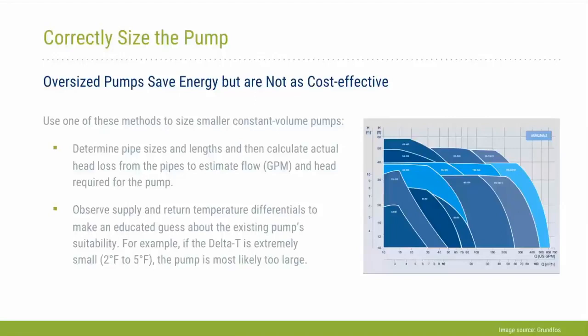I would say for a lot of these, you're probably going to see that the existing pump is oversized, and I would work with the manufacturer to help you right size that pump. As you can see for the domestic hot water ones, even though we had good energy savings, we got better savings and better economics by right sizing those. So it is tricky with these, but just something to look at there.